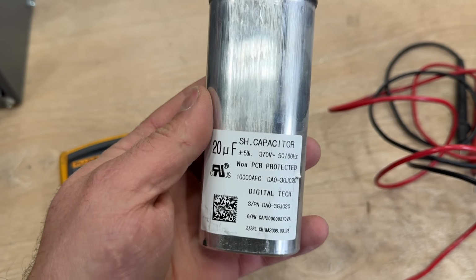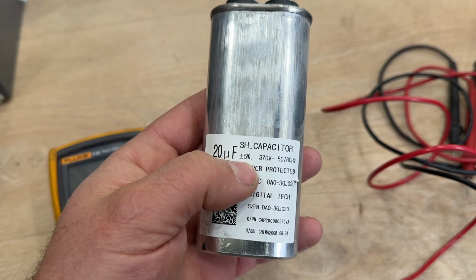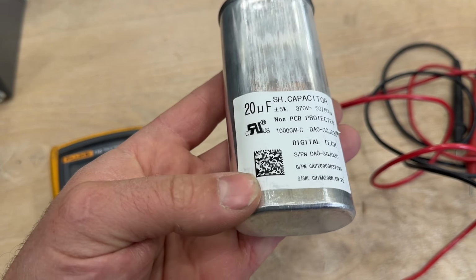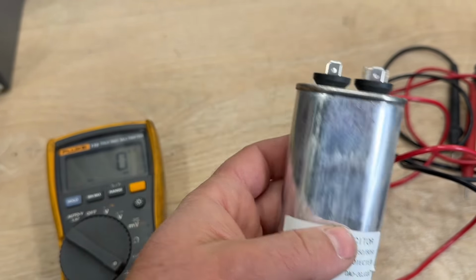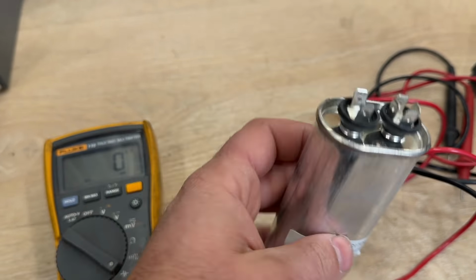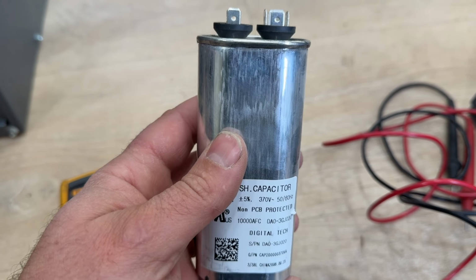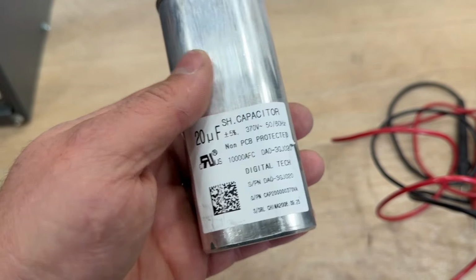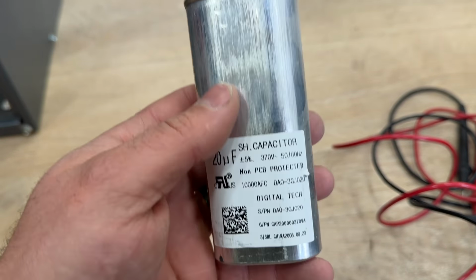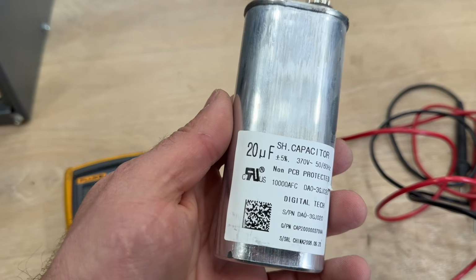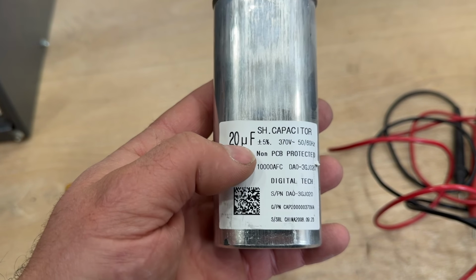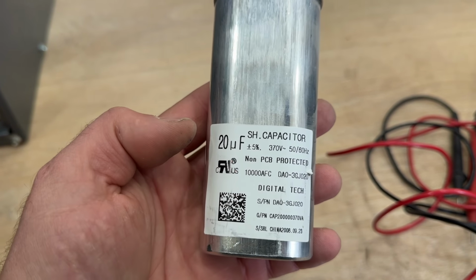This may have still functioned. It's just below the 5%. But if yours is reading significantly lower, or if it says OL on here, then your capacitor is absolutely bad. Some things you can also check for is if these prongs are not pointing straight up, if they're kind of mushroomed out and they're kind of pointing diagonally, that's a telltale sign that it's bad. Or if it's leaking fluid, or if it just looks terrible, it's probably bad. These are very cheap. You can buy these on Amazon. Just make sure that your rating and voltage matches, and you're good to go.